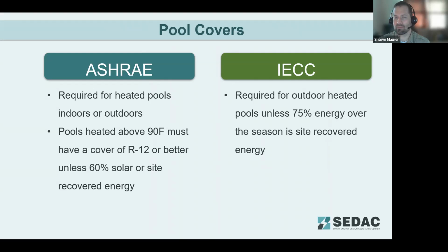Slight differences in the pool cover requirements here as well. ASHRAE requires pool covers for heated pools indoors and outdoors, where the IECC's applies to outdoor heated pools only. Pools heated above 90 Fahrenheit must have a cover of R12 or better, unless 60% of that energy is from recovered energy for ASHRAE. IECC's, again, is a little bit more stringent in the energy recovery requirement of 75%, but again, only for outdoor pools, not really considering the indoor condition. For warmer pools, such as therapy pools, that cover may have an increased insulation value, so we're looking at the R12 there for ASHRAE. IECC doesn't specify an insulation value for that pool cover requirement. It's mainly focused on reducing evaporation losses.